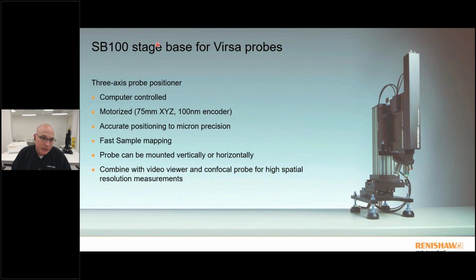When we're coupling out to the stage, just really quick, this is the 3-axis positional stage. We have 75 millimeters of travel in XYZ, and it's fitted with Renishaw Bionic 100 nanometer encoders here. So we get very high accurate positioning. We can still do our fast Raman imaging with this type of setup. And what I think is really unique is that you have free positioning of the probes themselves. You can either mount them vertically like they're shown here, or you can mount them horizontally. And what I like about that is that sometimes you have really big cryostats or maybe like an object on the wall and you want to analyze that. And so being able to just rotate that whole head and be able to do your Raman mapping in a vertical or in that horizontal position is something that I think is also really unique. You could turn it upside down. You could do whatever you like.